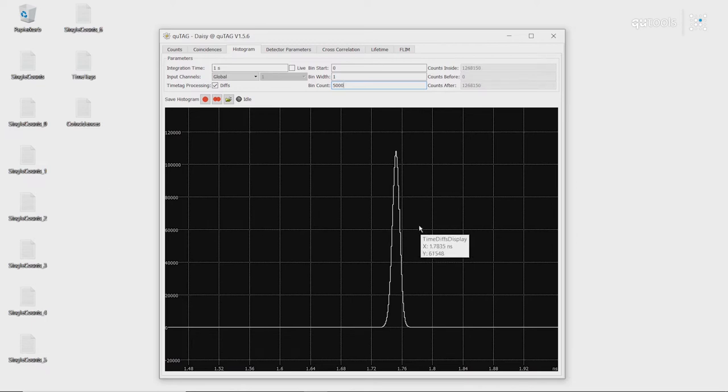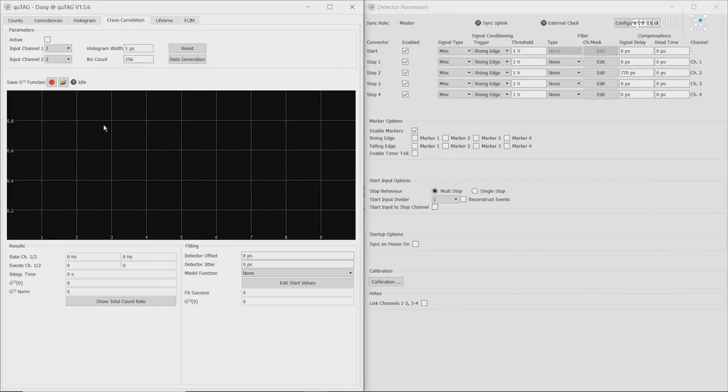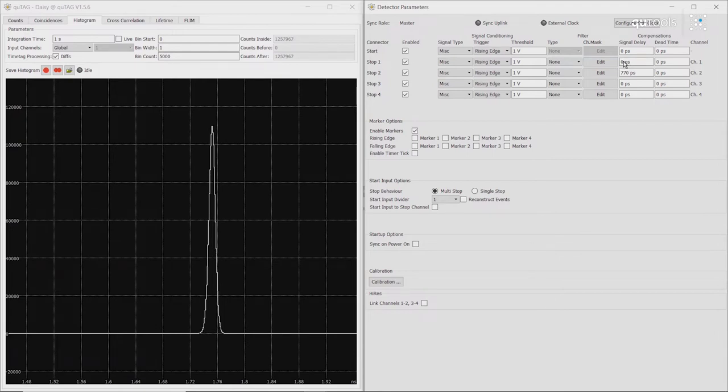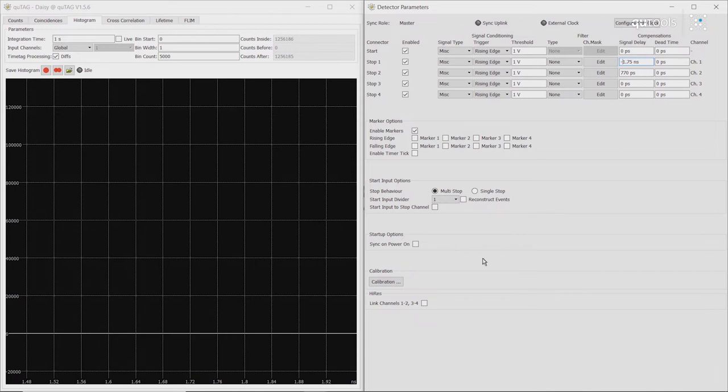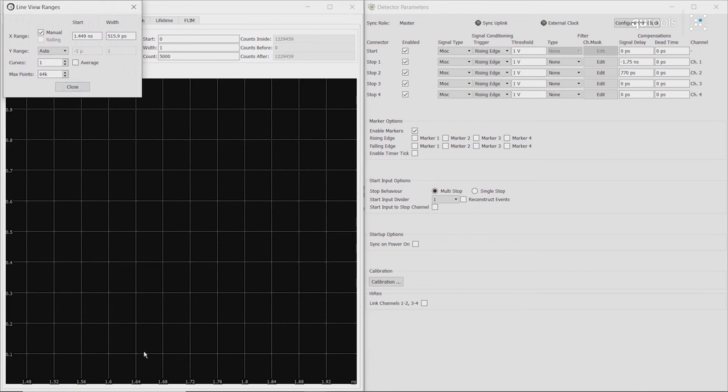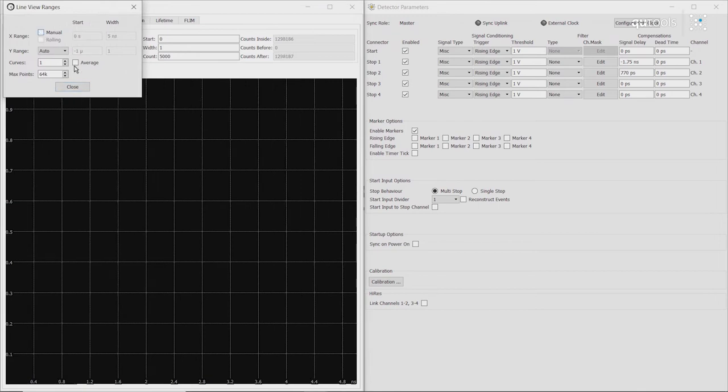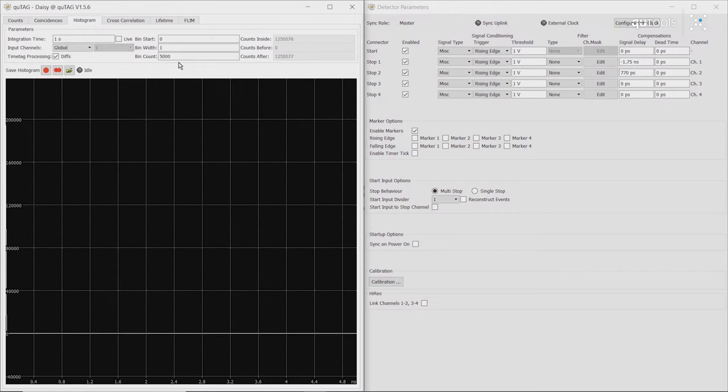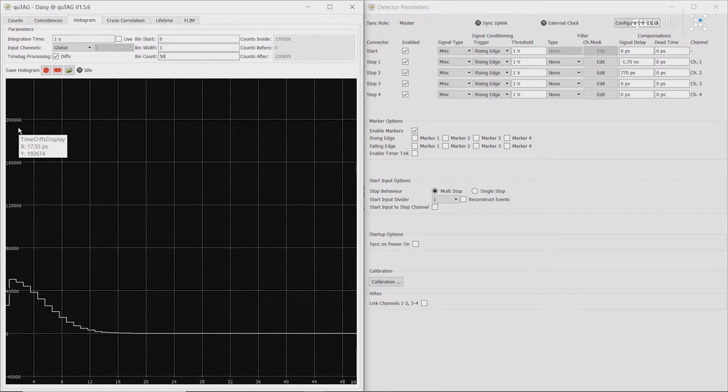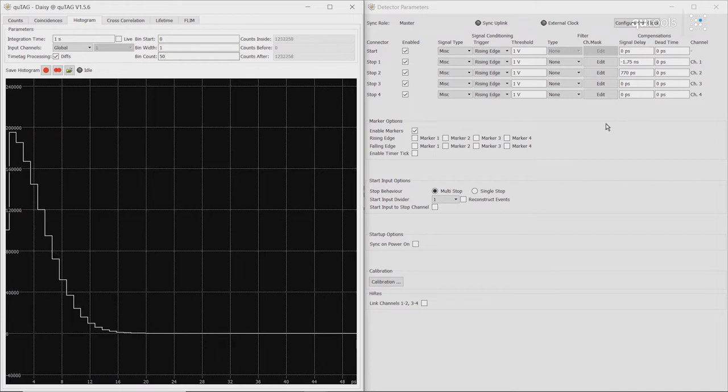If we wanted to correct for this, we can simply go to detector parameters and adjust the signal delay of channel 1 to the negative of that number. So 1.75 nanoseconds. As we can see, we no longer have any values at that range. So if we switch this back and we then adjust our bins again, we can see that our histogram is now centered around 0. So we've now corrected for the different cable lengths of the two channels.